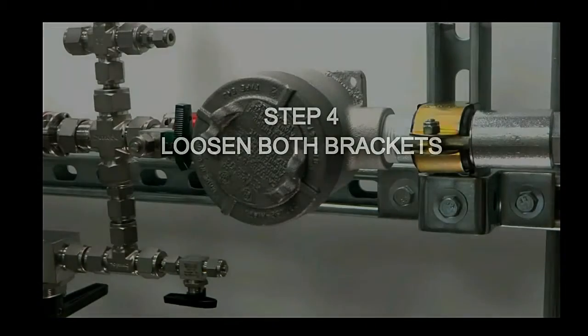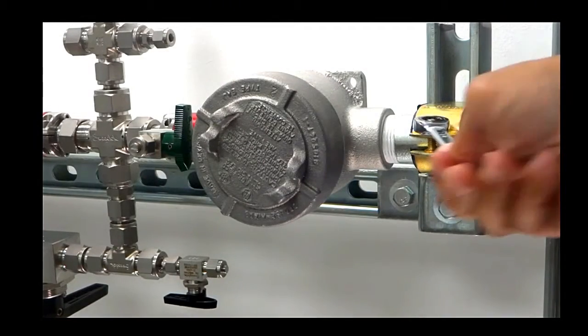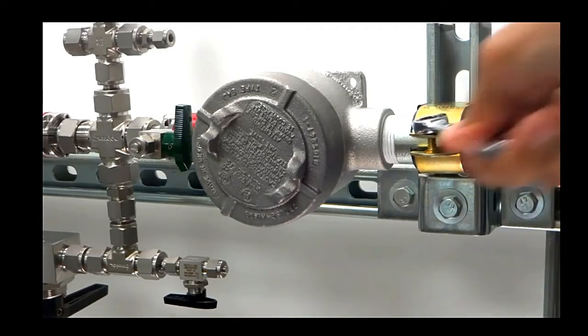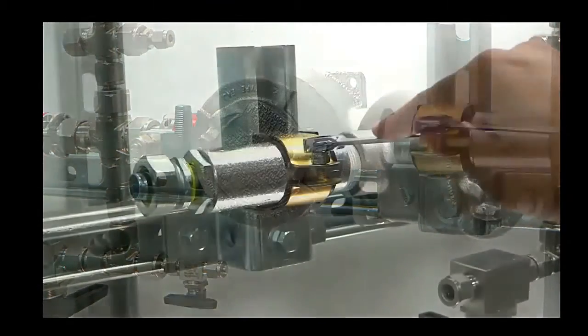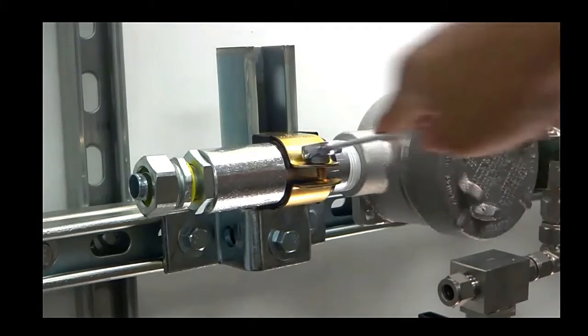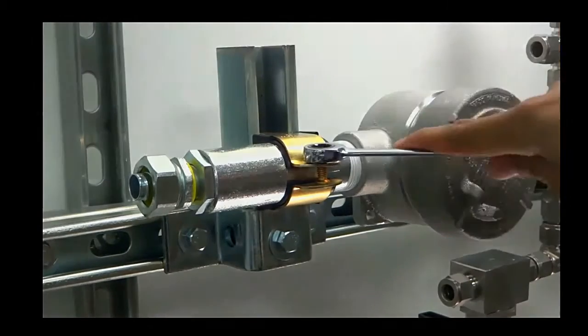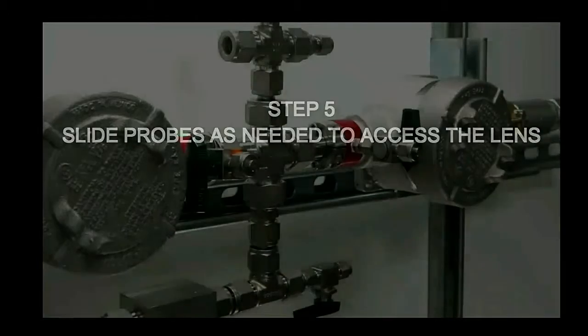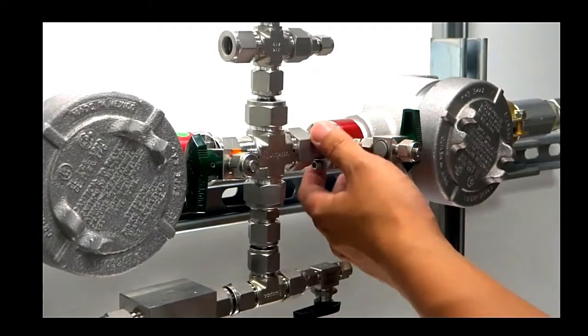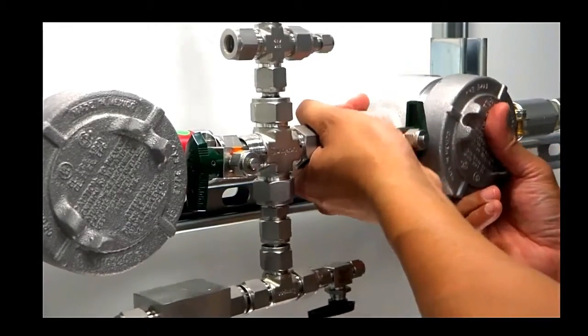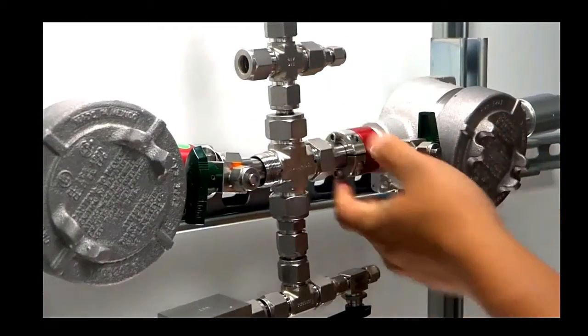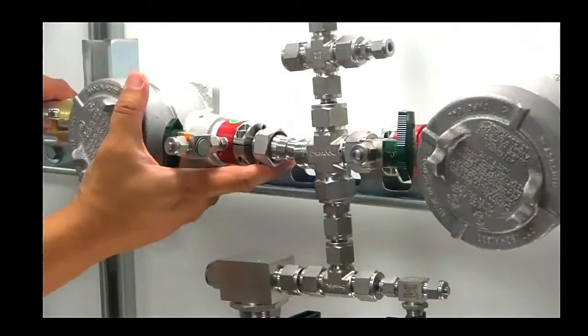Step 4. Loosen both brackets. The probe set assembly is held to its unistrut mount using 2 brackets. In order to access the probe windows, both brackets must be loosened, but not totally removed. Step 5. Slide probes apart. In order to gain access to the windows of the probes, they need to be separated. One side at a time, slide the probe set in its bracket, allowing access to the probe windows.